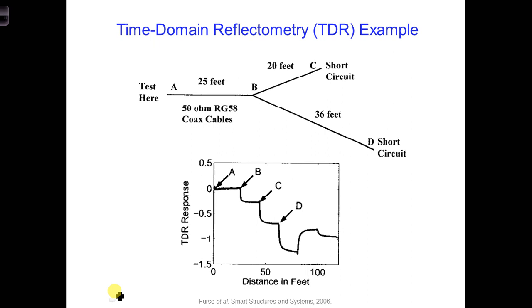When we study the reflections that occur along a conductor, it's called time domain reflectometry, or TDR. For a TDR measurement, a time domain reflectometer sends an incident signal down the conductor, and then the reflectometer records any reflections. Based on how long it takes for the reflections to reach back to the reflectometer, a distance to the impedance discontinuity can be determined.